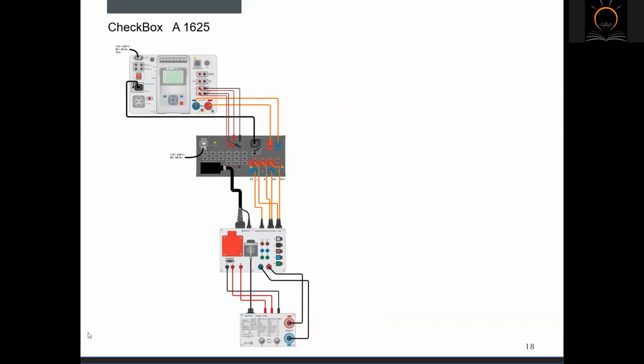Checkbox A1625. Checkbox or so-called verification box is an absolute must for every production line. Regular inspections reduce the risk of system malfunctioning and returning incorrect measurement results, which in turn can lead to defective, non-functioning, or even dangerous devices sent to the market. This can lead to recalls and unwanted costs. It is wiser to inspect the test system on a daily basis.